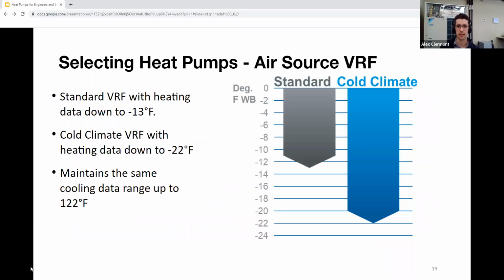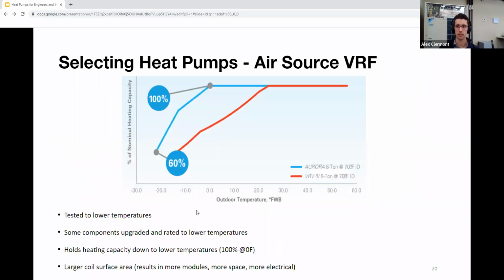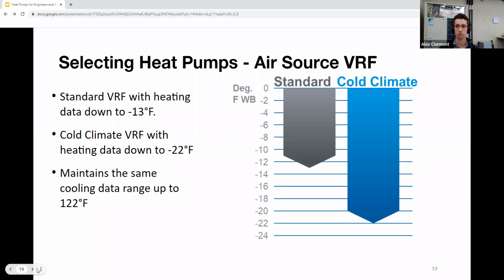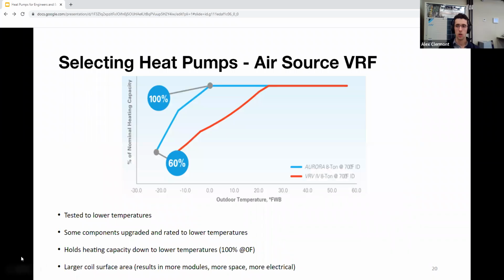Now, both of these machines, both the standard heating machine and the cold climate heating machine, have cooling operation up to 122 degrees. So there's no real change in cooling operation. It's all the differences with the heating data. So another little chart that we're going to look at is the difference between heating capacity of an 8-ton machine as a regular machine and as a cold climate machine. And both of them start out at 100% heating capacity. So that red line is showing the regular heating machine, and the blue line is showing the cold climate heating machine. And you see right around 25 degrees, the regular heating machine starts to have some sort of derated performance in heating capacity, whereas the cold climate machine does tend to keep its heating capacity all the way down to 0 degrees.